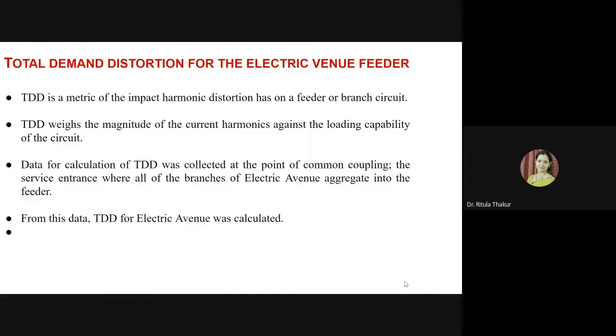So next, as I said, the total demand distortion is one of the more reliable metrics for the impact of the harmonic distortion on the feeder or the branch. Basically, total demand distortion weighs the magnitude of the current harmonics against the loading capacity of the circuit. The studies which were done were for all the separate charging stations, but total demand distortion takes into account the total demand loading capacity of the circuit.